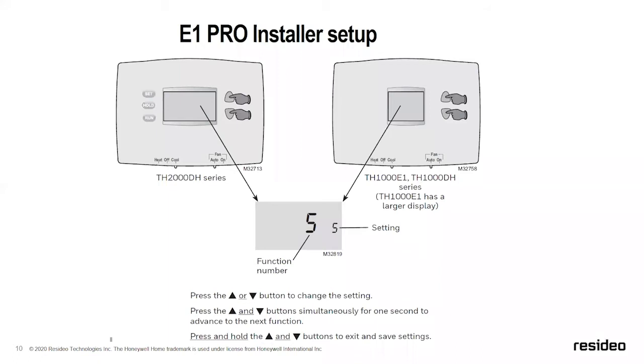For installer setup, when you first open up the box, it shows your installer setting options right out of the gate. If you want to get back into those settings later, hold the up and down arrows simultaneously until the display changes. Then use the up and down arrows to change the setting. To advance to the next installer setup option, hit the up and down arrows again simultaneously like an enter button. That's how you operate and set up the E1 Pro thermostat.